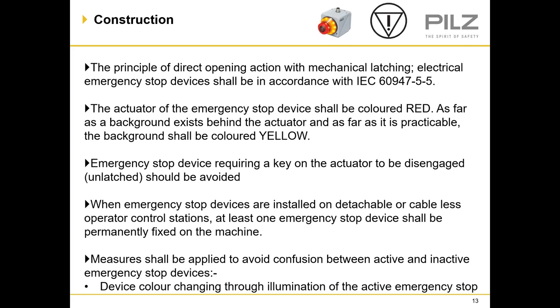Measures shall apply to avoid confusion between active and inactive emergency stop devices — the device should colour change through illumination of the active emergency stop. Emergency stops are no longer permitted to have writing on the yellow background but must display the Euronorm signal for emergency stop. Wireless emergency stops could potentially be taken away from the machine; if wireless emergency stops are used, then a hardwired emergency stop must always be available so someone else in the danger zone can access it. If the wireless e-stop leaves its operational zone, this must be indicated via a blinking light or change of colour.